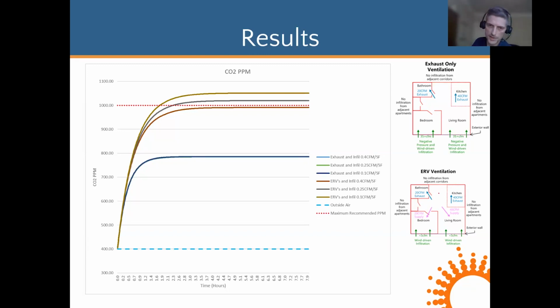With the ERV scenario, by design, we decided to provide only 20 CFM of supply air to the bedroom. That way we could meet our threshold for CO2, but we could have a slightly quieter air delivery. And because we're delivering the air more efficiently right to the bed area, we can then put more air into the living room where people spend more time. If we wanted to increase this rate to 30 CFM to be in line with the exhaust only scenario, these graphs would shift down and the curve would end up trending pretty evenly there.